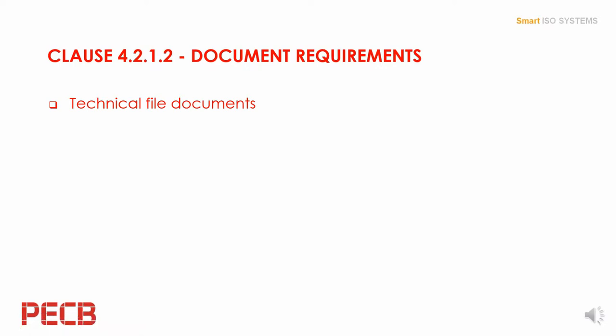There is a list of items A to Z, which is not exhaustive and can be used as guidance, as applicable, to meet the regulatory requirements. It lists 26 elements that ISO expects manufacturers to keep as part of the file, including product description, drawings, specifications, procedures, packaging instructions, instructions for use, labeling, clinical data. This technical file concept is not new, but the standard now will specifically require you to have it. In the past, this was addressed through the relevant medical device directive, but is now made explicit in ISO 13485.